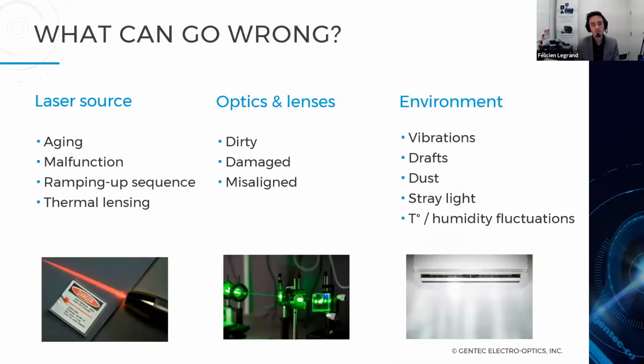Then there are a couple of things that could go wrong or not be as expected. For example, the laser source will age and could malfunction. You can see some ramping up sequences in the power output. You can see some thermal lensing effects as well that you need to take into consideration. And power measurement will be a really helpful, one of the main tools that you need to use to qualify and to quantify exactly this behavior. The optics and the lenses could get dirty, damaged, or misaligned. The environment will play a key role, with vibrations, air drafts, dust, light, temperature, and humidity fluctuations. So all of that needs to be taken into account when you want to build a laser system and build specifications that you could use for your research or sell to your customers.